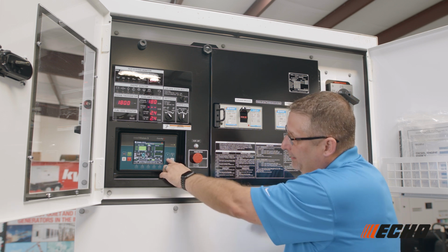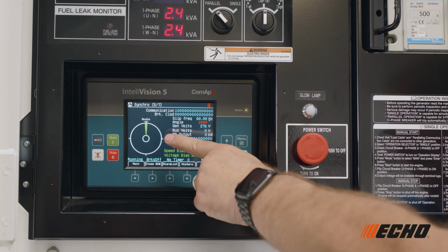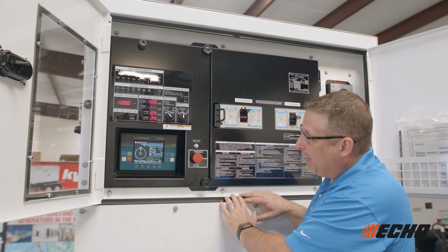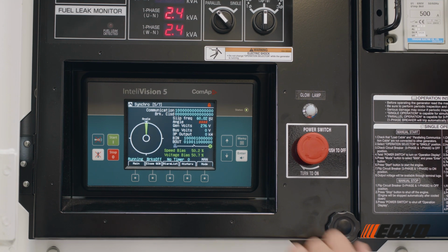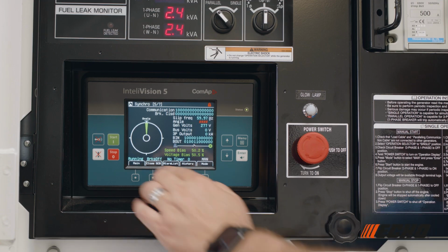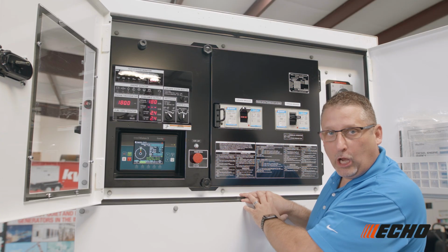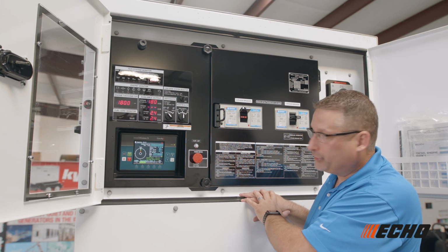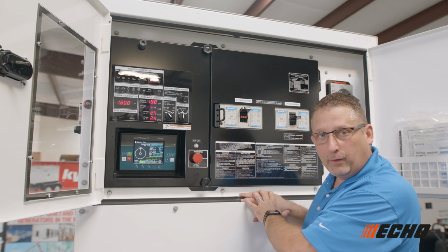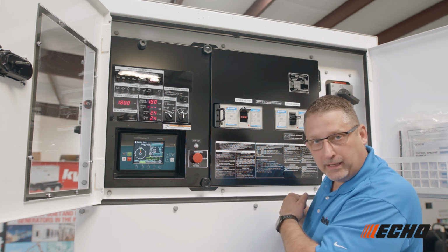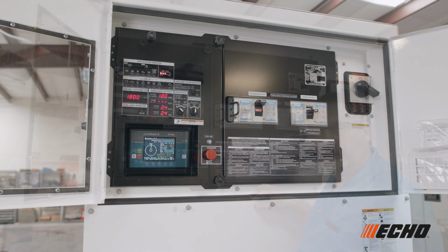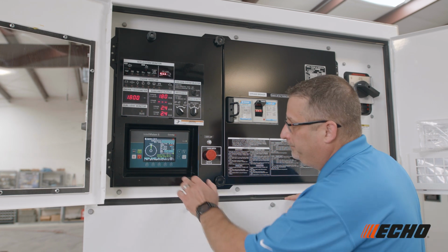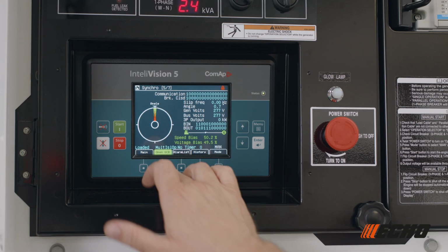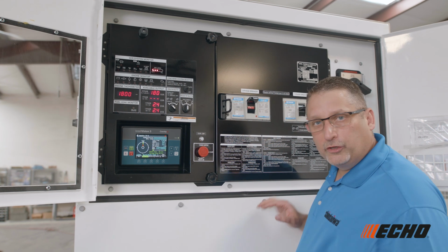Go to our sync screen. And from here, we're going to go ahead and close the breaker. You notice the contactor just closed, so this side is closed. We have to now go to Gen 1, and on Gen 1, we're going to make them parallel with one another. Let's go ahead and close the bus on Gen 1. The units are now in parallel.